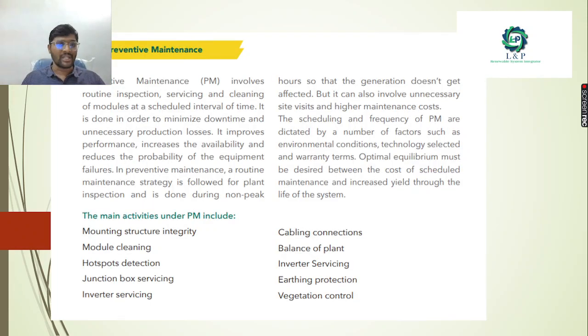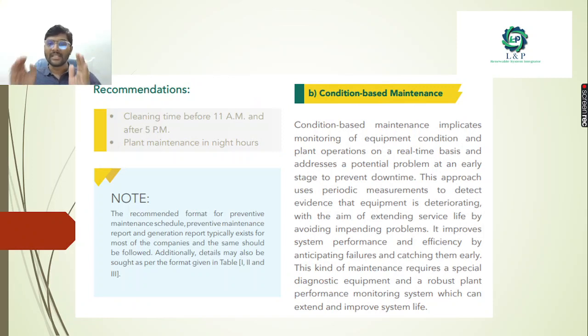So in preventive maintenance, the main important activities which should happen are mounting structure integrity, module cleaning, hotspot detection, junction box servicing, inverter servicing, cabling connections, balance of plant, earthing protection, and vegetation control. Okay, next, condition based.